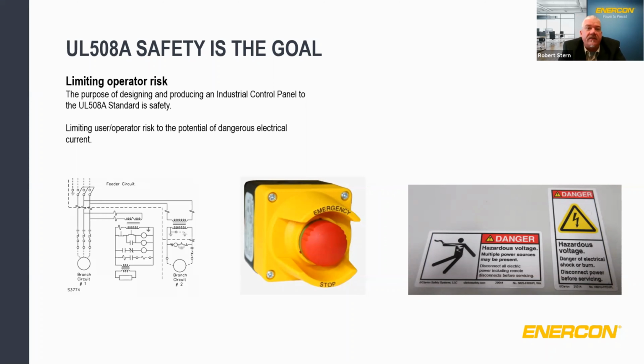The electrical design of the industrial control panel must comply with safe spacing, separation of circuits and conductors, and provide an adequate risk aversion and margin in calculations to ensure that the breakdown of components unintended to be interrupters is limited or removed. Next slide.